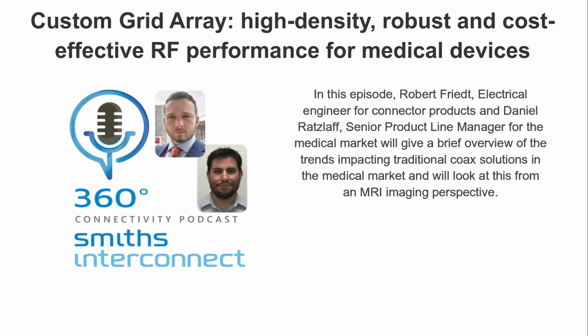There's also increased electromagnetic noise due to the higher field strength. The FDA has cleared MRI fields up to 7 Tesla, and research devices are out there with field strengths of 10 Tesla. This will continue to expand and grow as new MRI coils are developed to support these systems and are introduced into hospitals. And with the increased use of AI driving down turnover times, we can expect to see more patients per day. This increases the need for highly durable, high cycle life connectors.